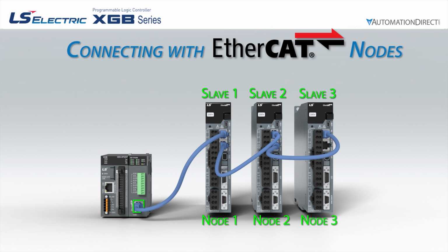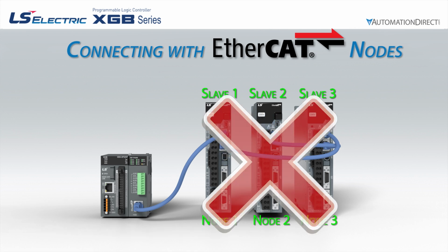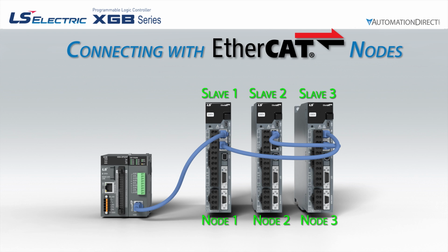the EtherCAT port on the PN08B card would have to be connected to the in port on the node 1 drive. The out port on that drive would have to be connected to the in port on the node 2 drive, and the out port on the node 2 drive would have to be connected to the in port on the node 3 drive. Connecting them in any other order will cause the controller to fault. It assumes a wiring mistake was made.